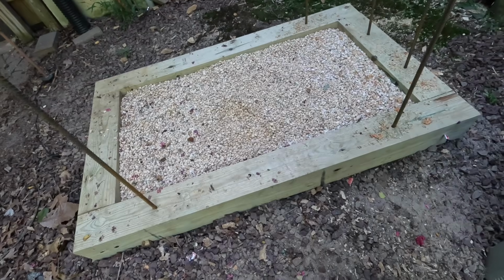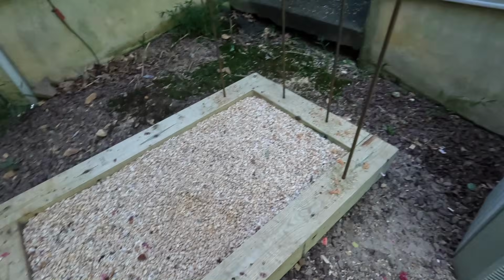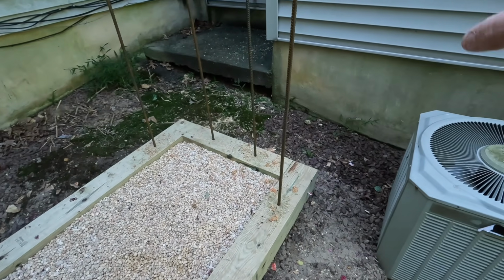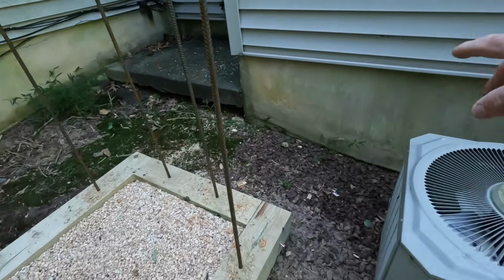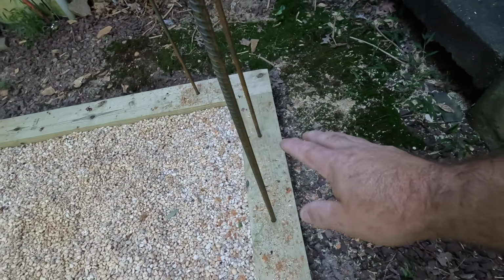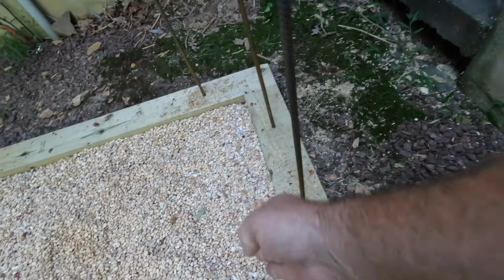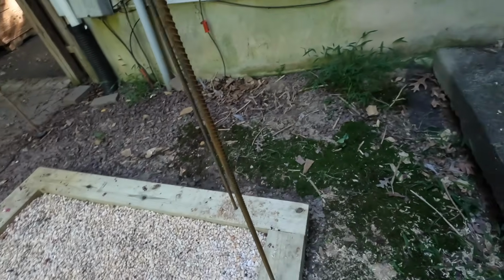So the generator is going to live right here. It's important that we be at least 3 feet away from the side of the house, since this will be the intake side of the air-cooled generator. Now you might say that looks less than 3 feet, but the generator will sit right here, and it's exactly right at 3 feet.